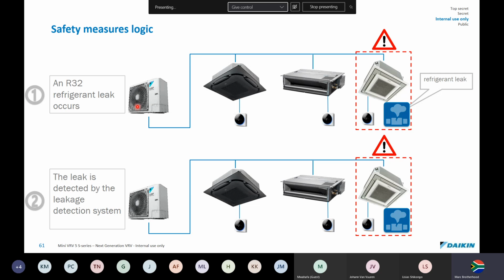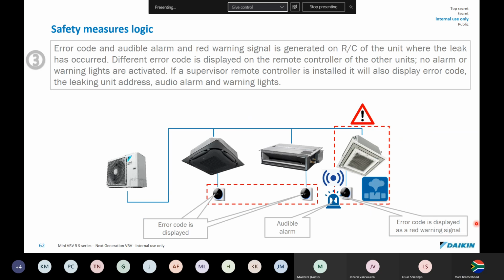So, safety measure logic: we'll see what happens if an R32 system leak occurs. Here's the leak, say in this guy's room. The leak will now be detected by the leak detection system, which is built into the indoor units. An error code, an audible alarm. So there's the little buzzer, and this is going to go red. It's going to make a sound. So the error code, an audible alarm, and red warning signal will be generated by the remote control of the unit where the leak has occurred.